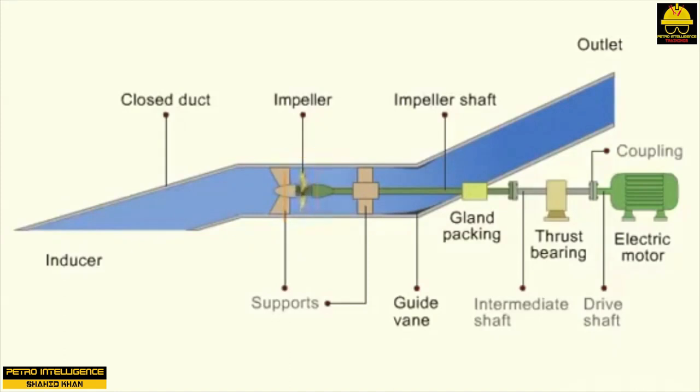A mechanical seal prevents leakage where the shaft penetrates the pipe elbow. A specially designed thrust bearing prevents axial movement of the shaft. Heavy-duty radial bearings support the pump shaft and prevent radial movement. Some axial pumps have thrust bearing oil coolers. An optional safety seal oil system or thrust bearing lube system is available for some models.